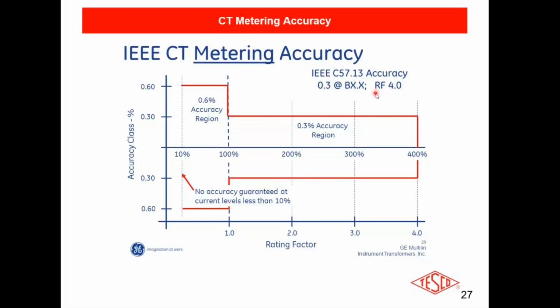You don't want to exceed it because it's a thermal rating factor. You exceed 400%, and you're going to start doing bad things to the windings in that transformer. You're going to start breaking down some of the insulation. You're going to damage your transformer. As long as you stay below 400%, it's going to maintain its accuracy very flatly. It's amazing when you test them. It is amazing how accurate they remain.